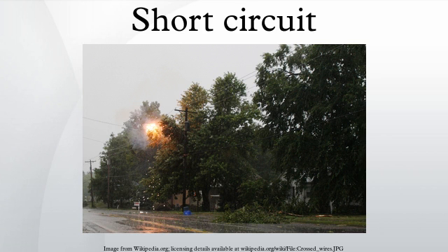Such short circuits are likely to result in a very high current and therefore quickly trigger an overcurrent protection device. However, it is possible for short circuits to arise between neutral and earth conductors, and between two conductors of the same phase. Such short circuits can be dangerous, particularly as they may not immediately result in a large current and are therefore less likely to be detected.